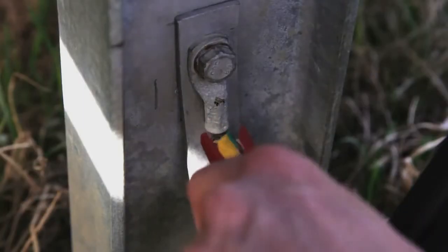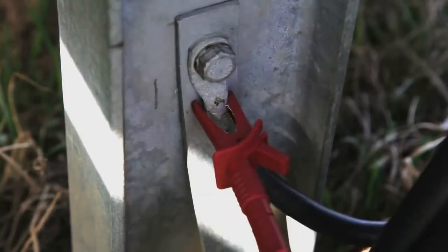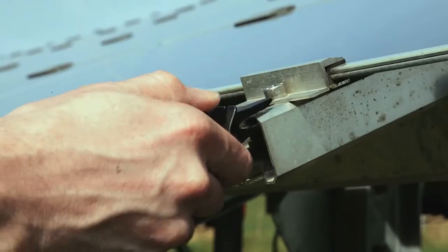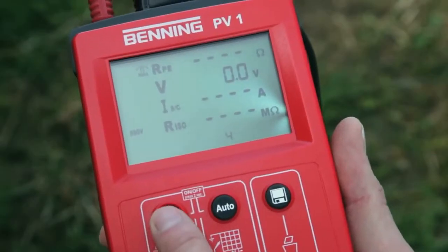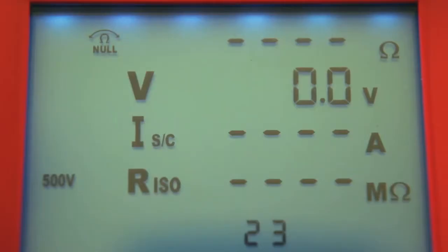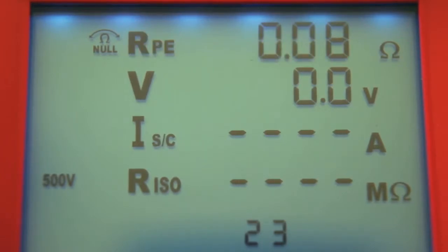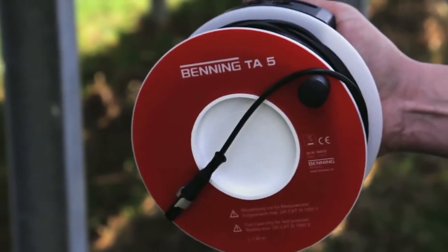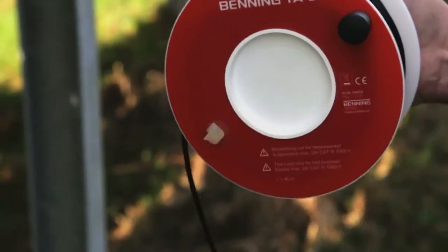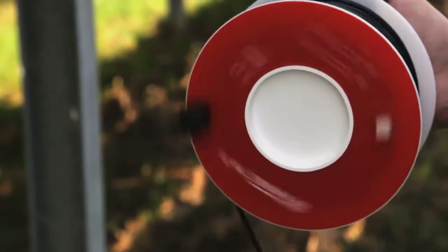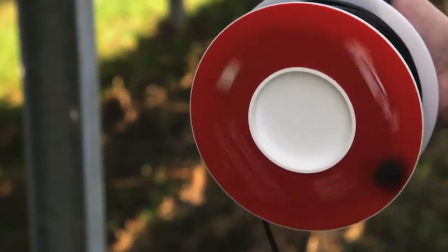For earthing measurement, connect the red alligator clip to the main earthing connection and the black alligator clip to the module frame. Press the RPE key and read the measured value on the display. For larger distances, it is recommended to use the optionally available 40-meter measuring line Benning TA5.